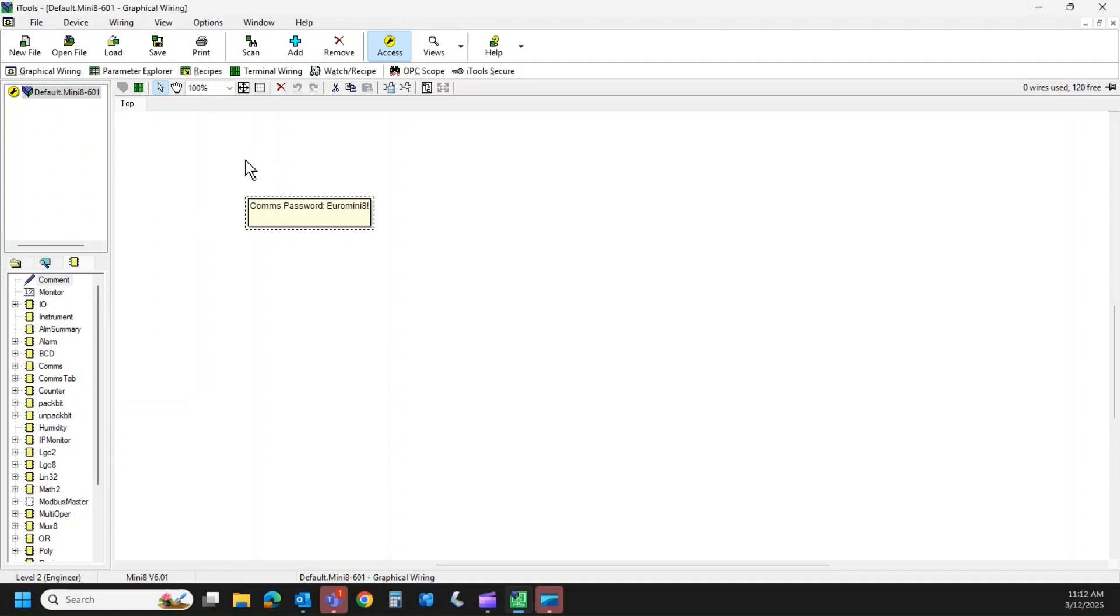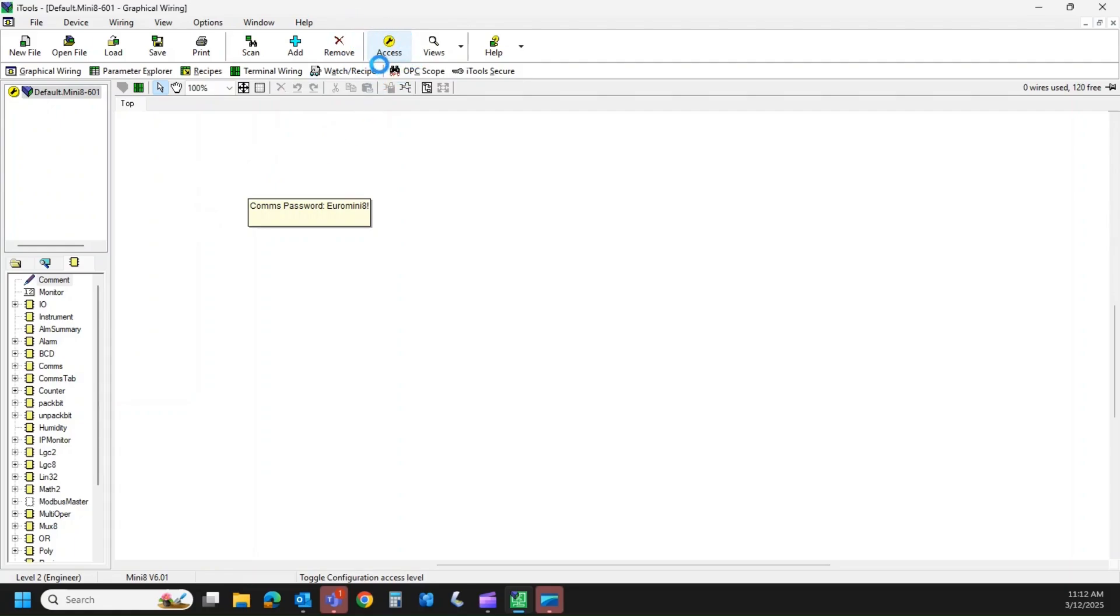That is really it. So it is there. I can get out of access mode. So in this access or configuration mode, you see the yellow background with the black wrench. While it's in that mode, once you have a configuration loaded into it, the controller will not control the process while it's in configure. So you have to get out of it and go back to operator mode. And then the unit would control.